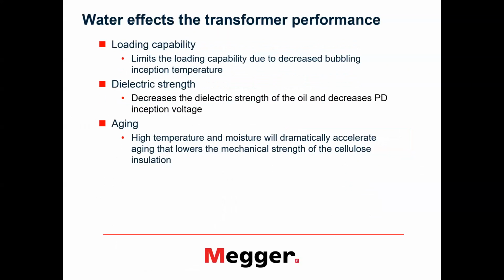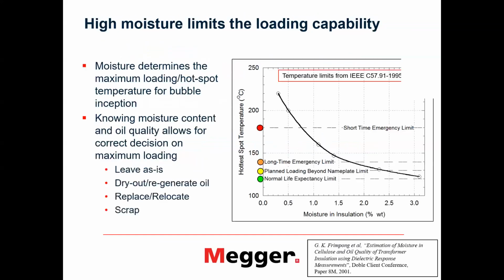The presence of water affects the performance of the transformer. The loading capability is impaired. We cannot load it as hard as we would like to due to decreased bubbling inception temperature. The dielectric strength also decreases if we have moist paper and subsequently also moist oil. Also the PD inception voltage will decrease if we have a presence of water. And of course, aging is one of the factors which also comes into play when we have moisture and temperature. We just accelerate aging of the cellulose itself, which becomes brittle and disintegrates, and the transformer eventually loses its mechanical strength along with dielectric strength. So this is something we want to avoid.